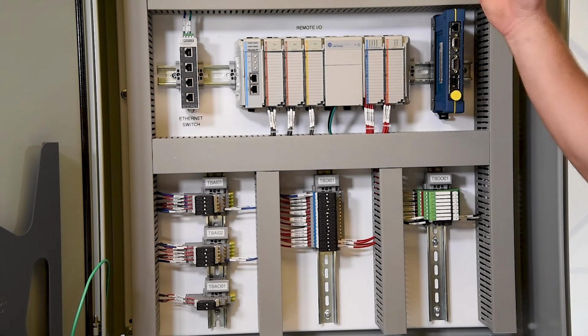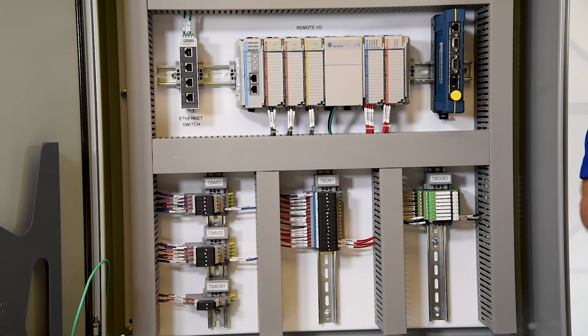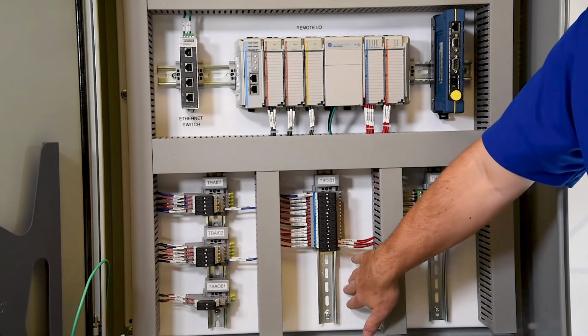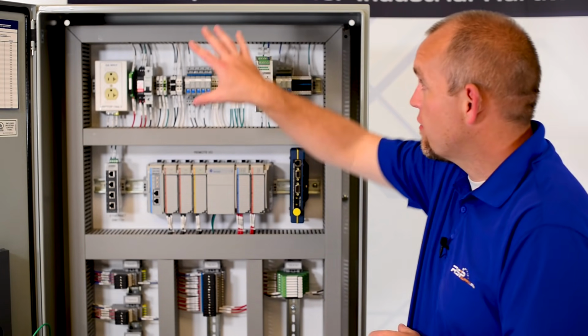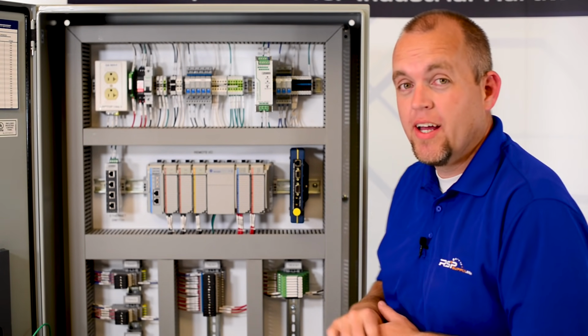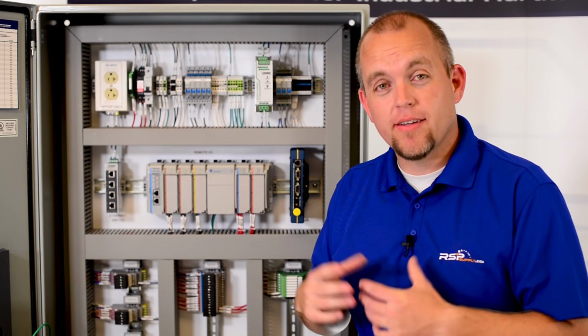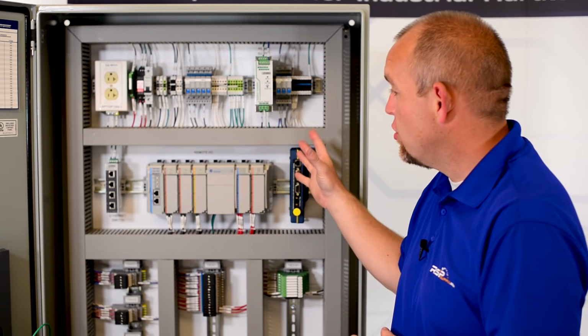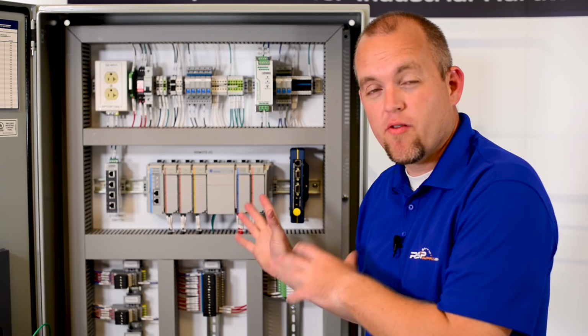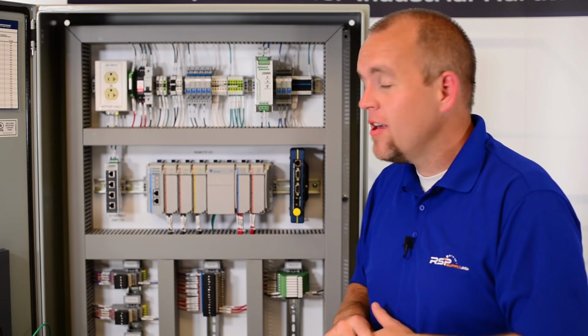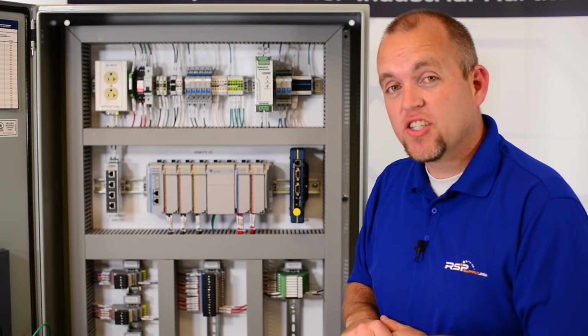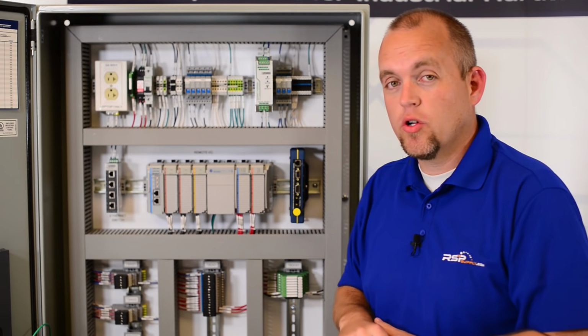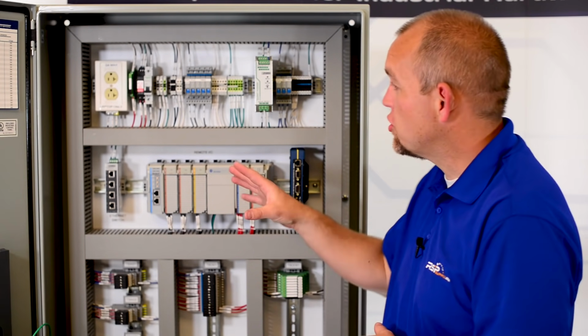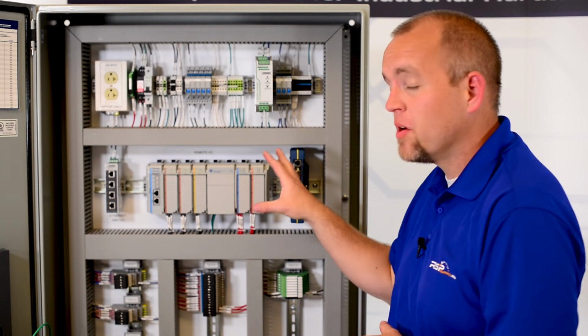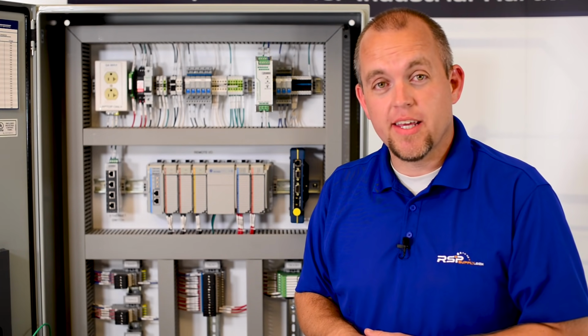All of the components within the panel, including the wire ducting and DIN rail, are mounted to what we call the backplate. The backplate is separate from the actual electrical enclosure itself. And what the backplate allows us to do is fabricate, build, and wire this panel separate from the enclosure. When we're ready, we can take the backplate and all the attached components and put it in the electrical enclosure itself. The electrical enclosure provides protection for both the components and any operators in the area.